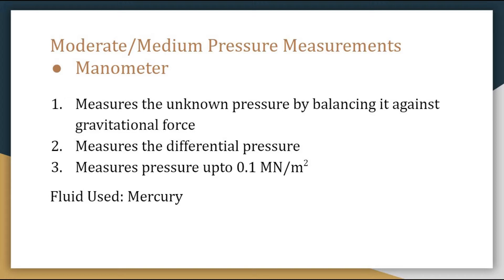A manometer is something which measures the unknown pressure by balancing it against the gravitational force of liquid heads. It is used to measure dynamic pressure as well as differential pressure. Manometers can be used to measure pressure ranging from as low as vacuum to a high pressure of about 0.1 mega newton per meter square.